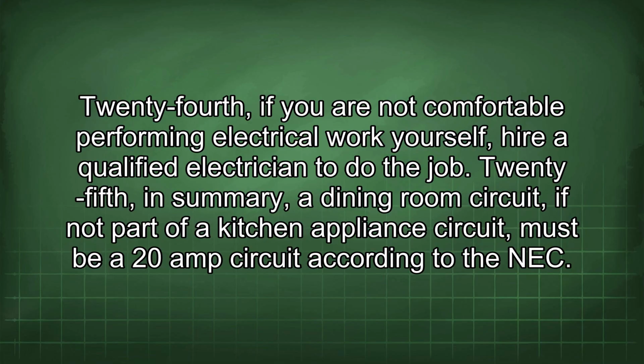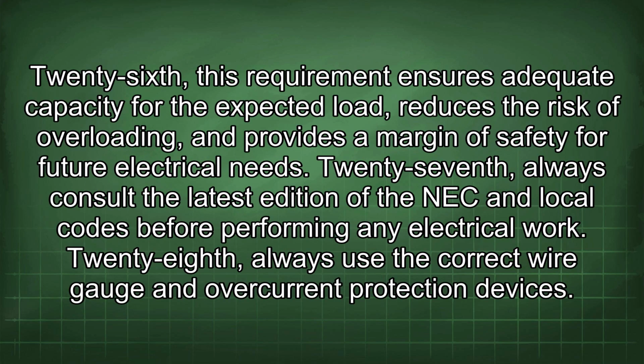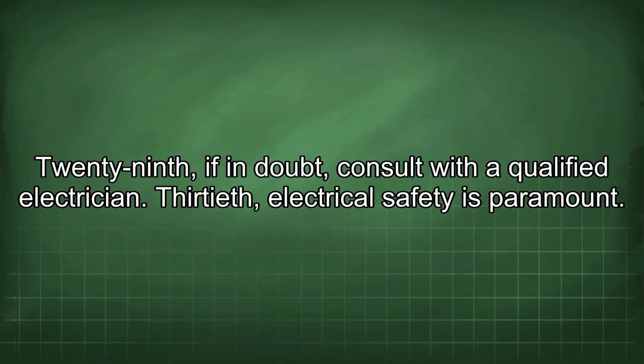Twenty-fifth, in summary, a dining room circuit, if not part of a kitchen appliance circuit, must be a 20 amp circuit according to the NEC. Twenty-sixth, this requirement ensures adequate capacity for the expected load, reduces the risk of overloading, and provides a margin of safety for future electrical needs. Twenty-seventh, always consult the latest edition of the NEC and local codes before performing any electrical work. Twenty-eighth, always use the correct wire gauge and overcurrent protection devices. Twenty-ninth, if in doubt, consult with a qualified electrician. Thirtieth, electrical safety is paramount.